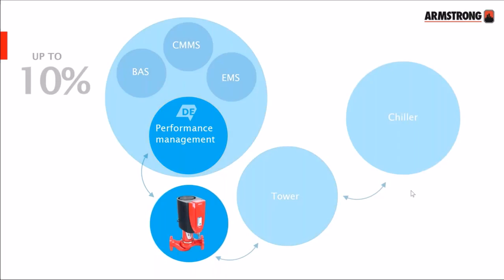By starting with an upgrade to intelligent pump, so by following that pump first approach, on the distribution side of the system, we get a much better understanding of the building load, the characteristics of the system and its components. And this immediately brings us a number of things. As we previously saw, it brings us up to 10% energy savings. It also makes the system operation transparent to the BMS system, and there's many benefits to that, of course. And like a healthy heart, it adds to the efficiency of other equipment in the system by ensuring optimal flow to towers, chillers, etc. And most importantly, it can be cash flow positive, or a cash flow positive investment from day one.